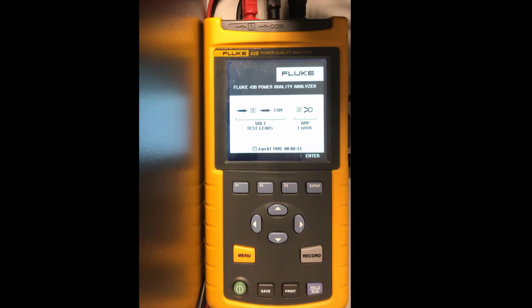So notice what happened when I first turned this on. The power analyzer wants to confirm that I have 1-to-1 voltmeter leads connected, and that I have a current clamp connected to input 2. So it's confirming that, and we know that's correct. But what we need to do is go in and make sure that the calibration settings, or the sensitivity settings, are properly set for the configuration we're going to use. So that's what we're going to do now. So then you just hit the enter button, and then you're going to go to menu.